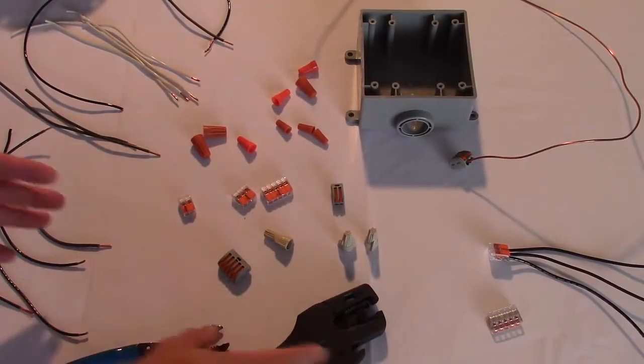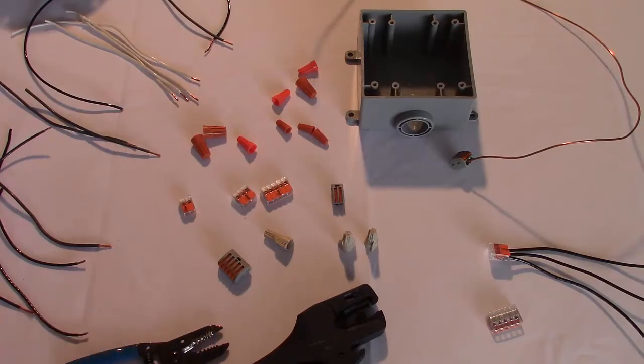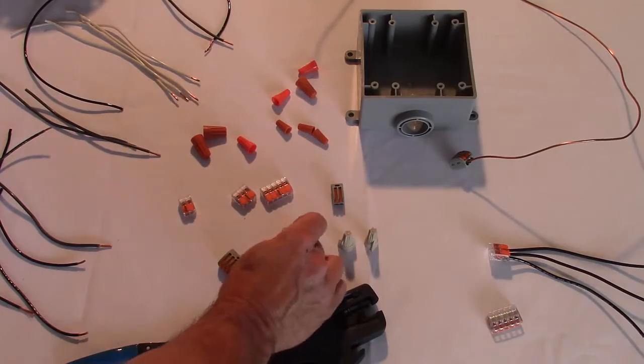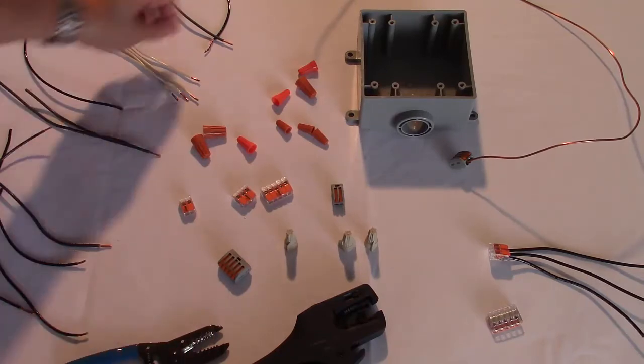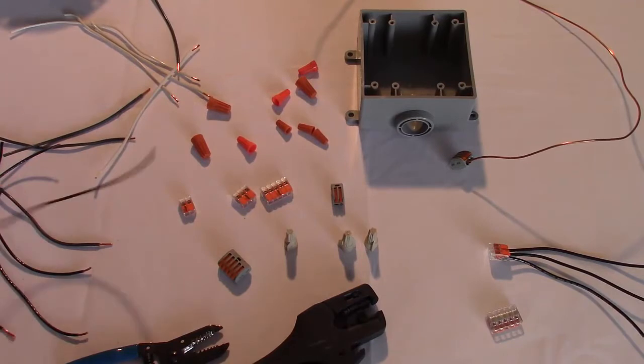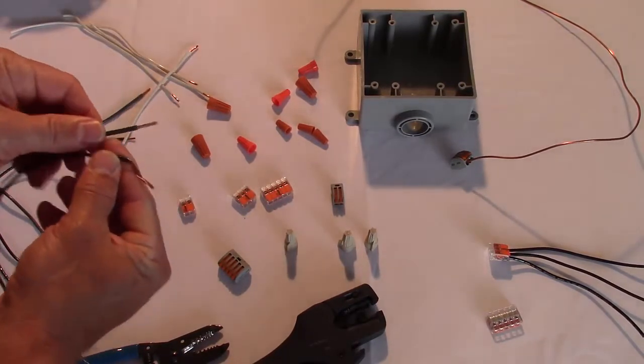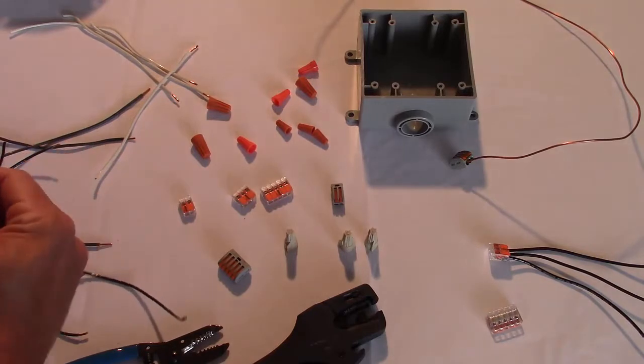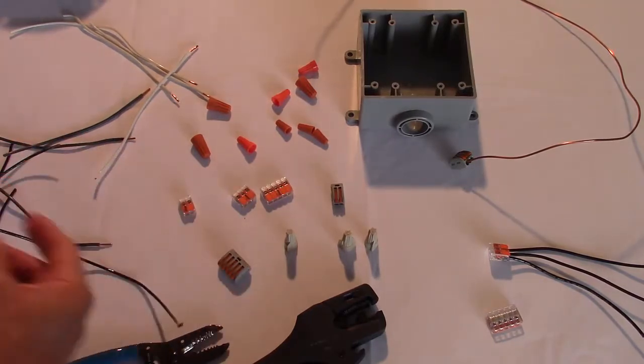Okay, so another thing we want to look at is when you're actually handling the conductors once you've got the proper strip length or what you hope is with the twist type connectors. How do you insert or connect these wires together? For example, as I mentioned previously, if you have a stranded conductor and a solid conductor that you have to bring together, which often happens, you have to strip them to different lengths with the twist type connectors.